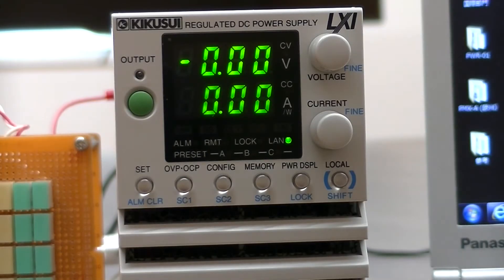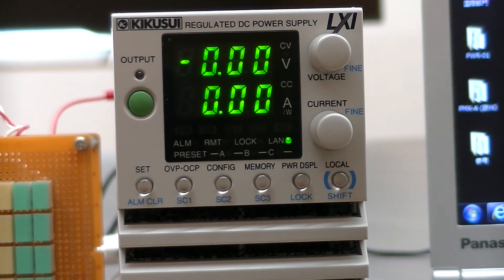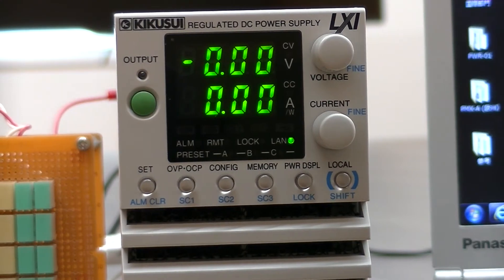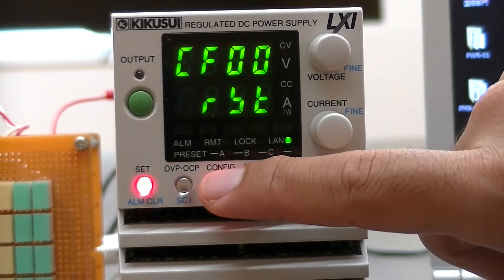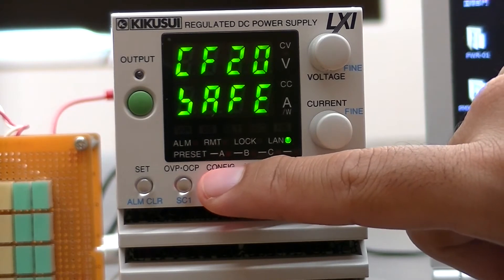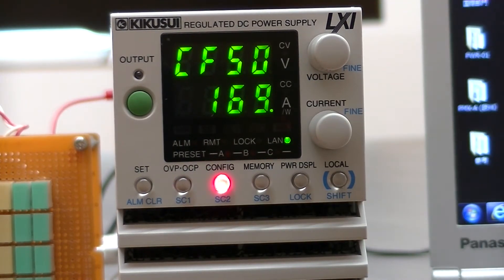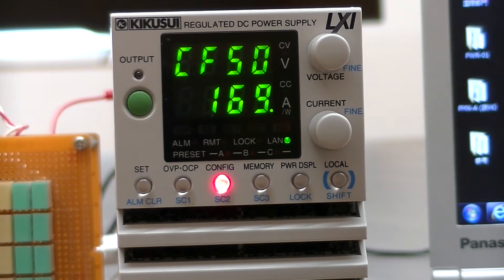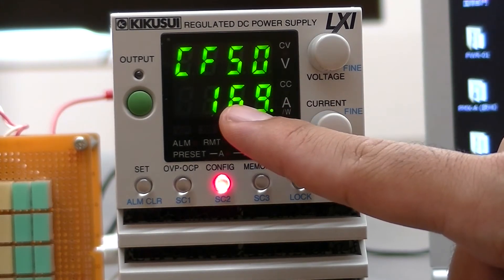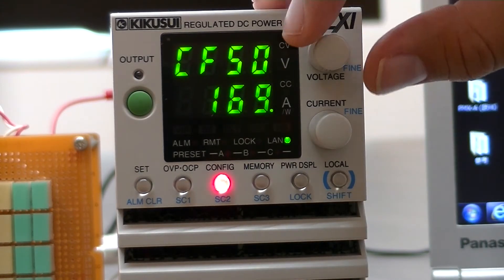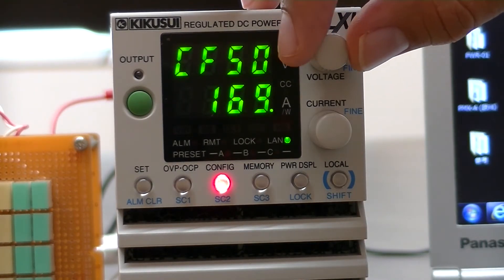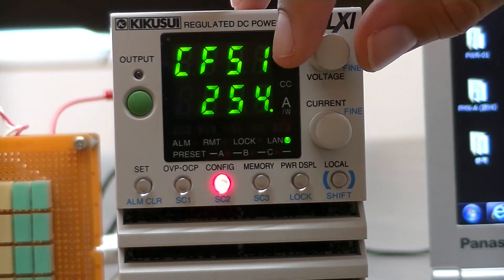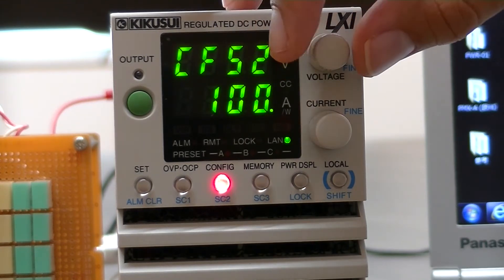Now once you have installed the visa and connected the LAN cable to both PC and the PWR01, you need to set up the IP address. This is done by selecting config 50. Usually it will take a while for the IP address to appear. Once you see the number below config 50, then you can scroll through config 50 to 53 to get the full IP address.